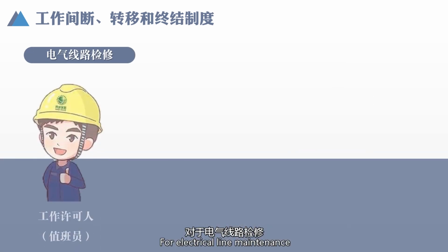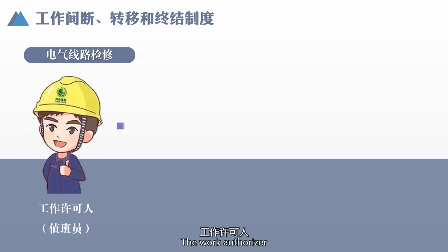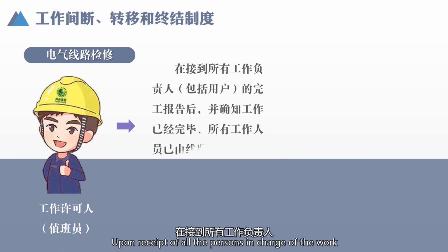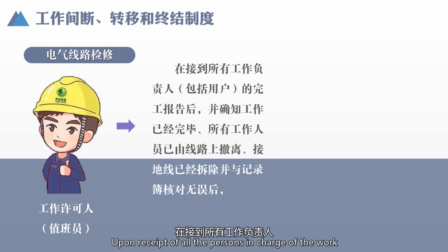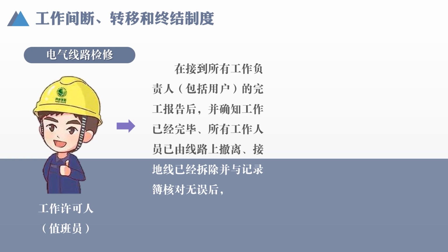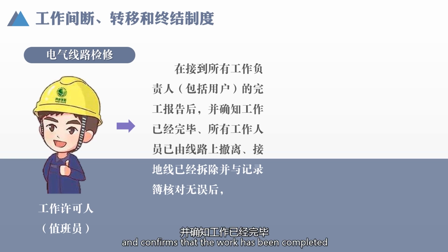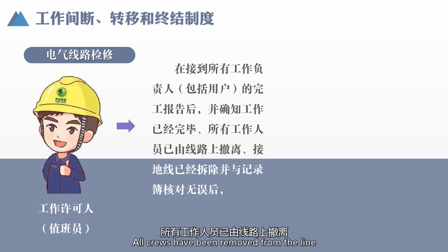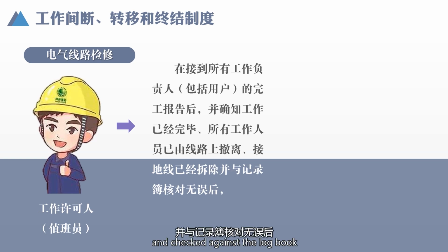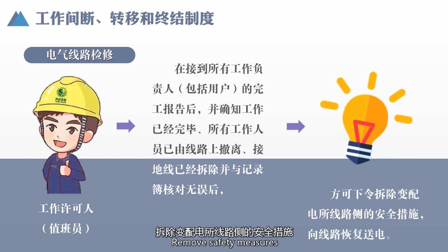For electrical line maintenance, the work authorizer, upon receiving reports of completion of work from all persons in charge, including the user, confirms that the work has been completed, that all crews have been removed from the line, and that the grounding wires have been removed and checked against the logbook. only then may they order that safety measures on the line side of the substation are removed, and power is restored to the line.